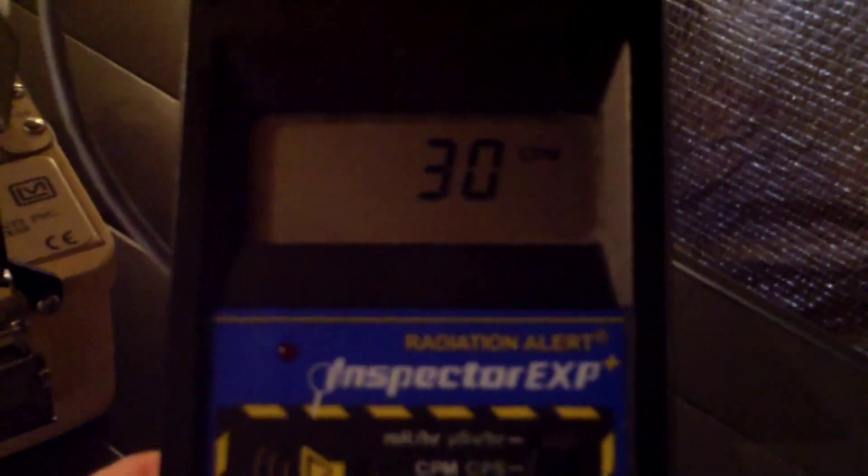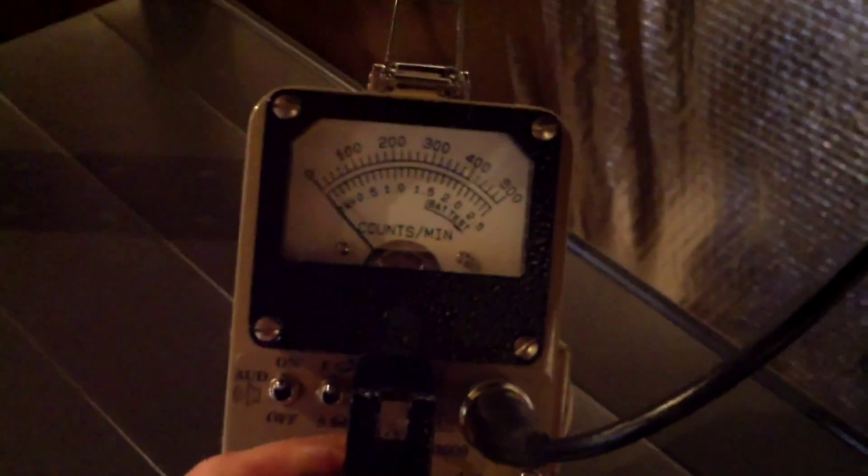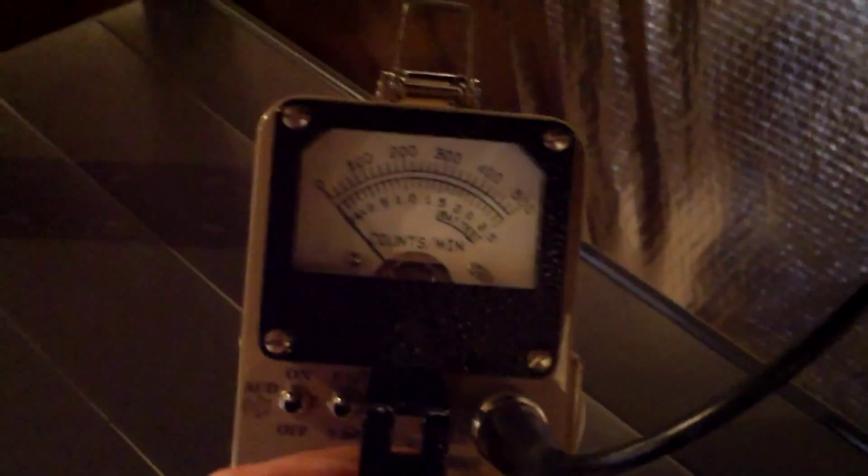Statistically, if I were to run this detector for maybe an hour or two, I would probably pick up a slight increase, but it's definitely down to normal. It's around 34 counts per minute's normal, so it's going up and down. Let's look at the Ludlum. This is much more gamma sensitive. It's getting its normal background, probably.